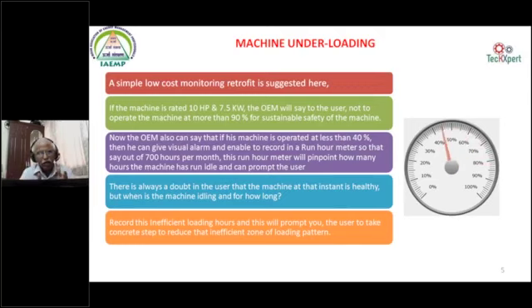But when the machine is going for underload, let us say it's a 10 HP motor, for almost 10 hours of the day it is running at less than 40%. And for another 14 hours, as it's a 24/7 machine, let us say, it is running at 70%. So any motor in the industry which is running intermittently should have a run-hour meter and a kWh meter. The Bureau of Energy Efficiency targets only one thing. Before, they were talking about 10 HP motors, but now things are changing as tariff rates are going up. Even for a 5 HP motor it is worth it, because metering prices have come down. With a run-hour meter and a kWh meter on any 5 HP motor and above, automatically you know how many hours the motor has run and how many units per day it has consumed. So you know the average loading of the motor.